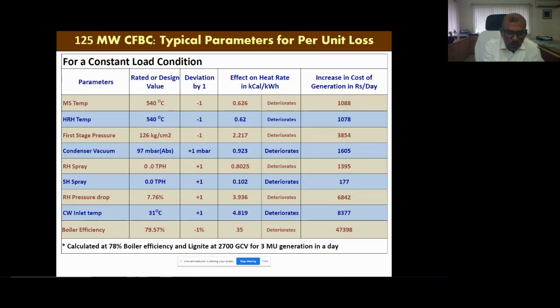The most important one I would like to highlight is the last one, the boiler efficiency, 79.57, which is lower considering the moisture factors, because the moisture is more than 45 to 52%. There the heat rate loss is 35 kilocalorie per 1%, and the amount is 47,398 rupees per day per unit. If you evaluate this on a year basis, considering 310 days of operation, about 85% availability factor, this loss will be in the range of 5 to 6 crores. So a 1% efficiency drop is causing 5 to 6 crores. We calculated this based on our experience at 78% boiler efficiency and lignite GCV of 2,700, for 1 unit, with 3 million units of generation in 1 day.